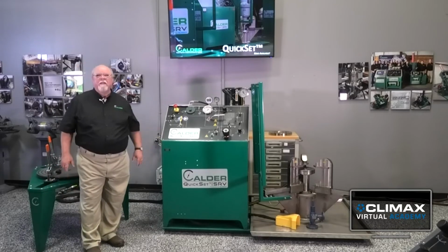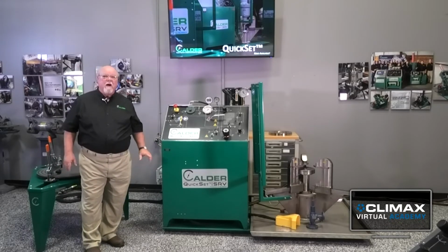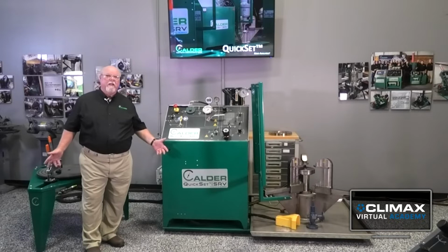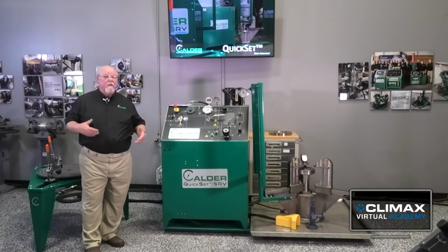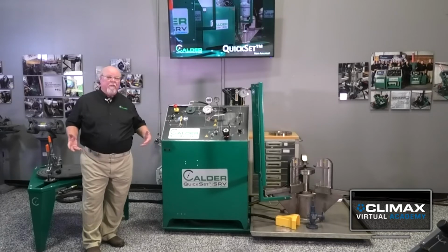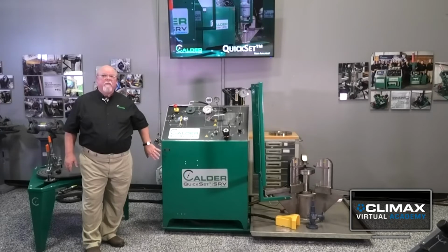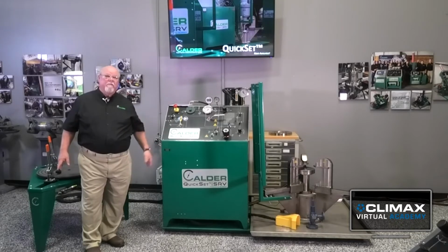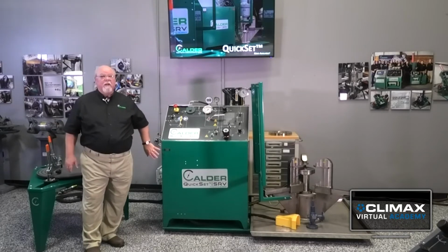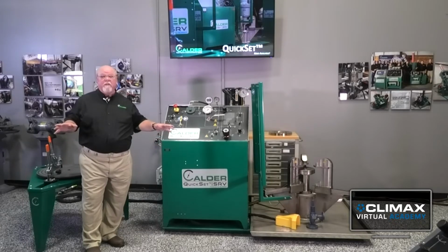The unit to my left is a best-in-class, compact, rugged, modular SRV tester that provides mobility and industry-leading value. Hopefully by the end of today, you'll be able to see how all that value is imparted into the machine. This unit can test, set, and certify pressure relief valves up to 6,000 PSI on not only gas, but can do liquid. And with the right attachments, we also can provide vacuum breather valve testing from full vacuum up to 100 PSI. This is a completely configurable product platform offering several base machines based on your application, your needs.